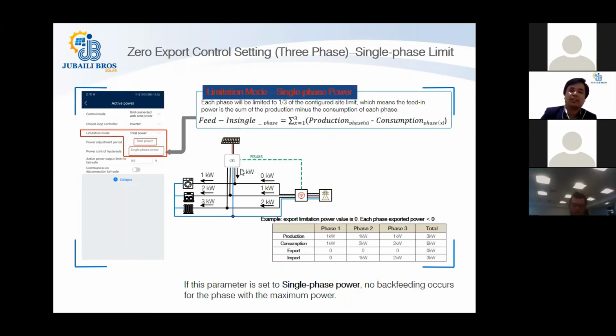If the generation on all three phases is, let's suppose, 4 kilowatts, the inverter will limit itself based on the phase which has the highest generation. On that phase there will be no backfeeding occurring, but on the other two phases where the load is less, there might be backfeeding occurring. So this is another type of control option that you have.